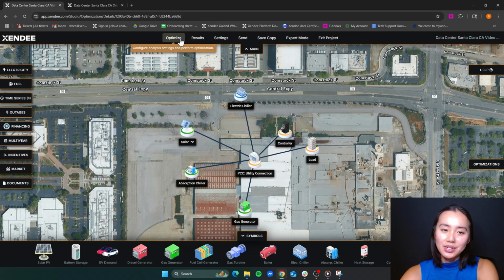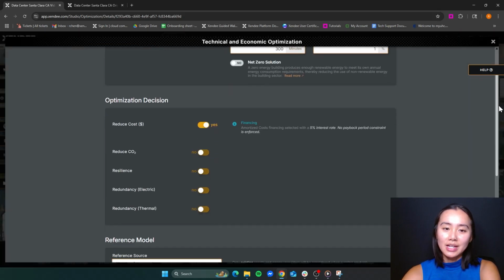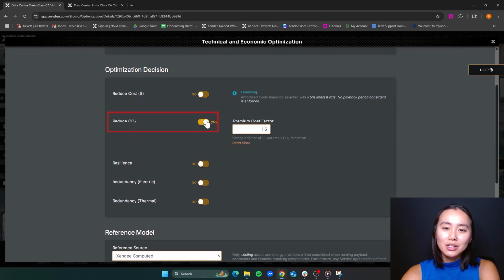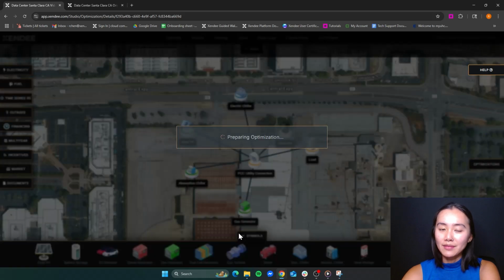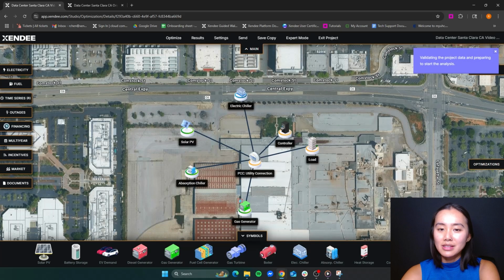In the Optimize window, we can select Reduce CO2 as our objective. When you select Reduce CO2, you will also see a premium cost factor input. The premium cost factor defines how much more we are willing to spend compared to the reference case in order to reduce emissions. I set a premium cost factor of 1.1 of the base case, meaning I'm willing to pay 10% more in annual costs compared to what I would normally pay to operate my existing data center.